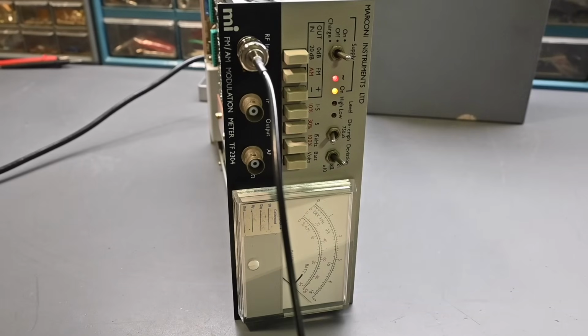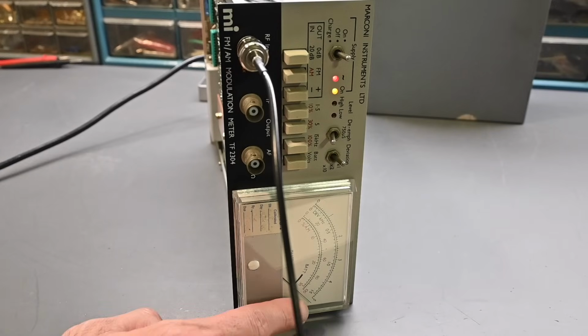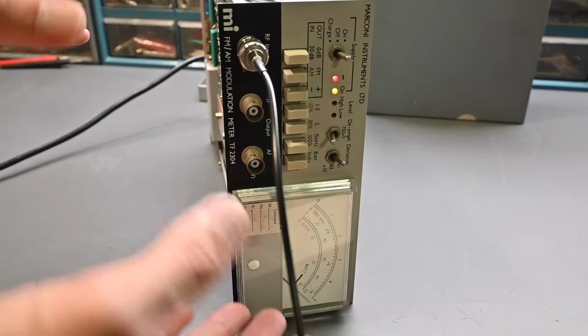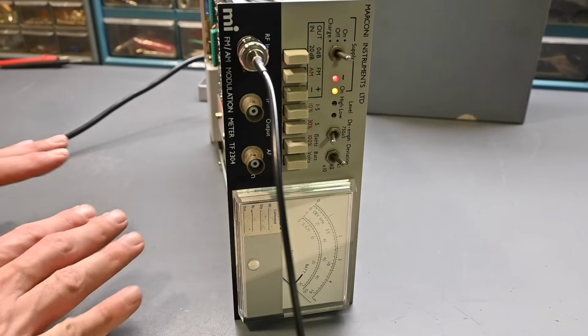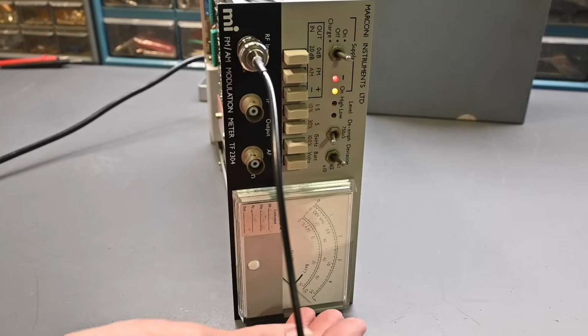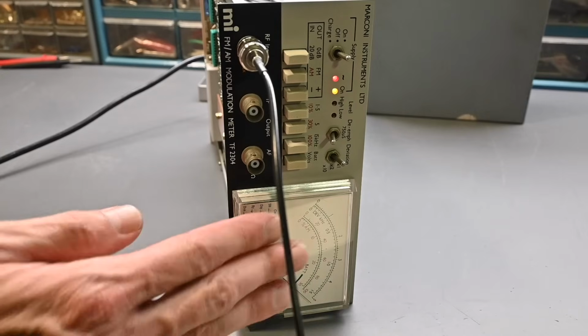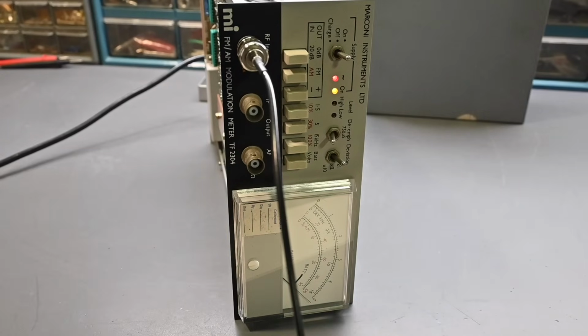So like before, it's at 300 megahertz, 5 kilohertz for the deviation, 1 kilohertz tone, and 0 dBm output. So full scale indication here. What I'll do is I'll make the adjustment and I'll turn the meter down flat and take a look at the setting, because with this turned sideways like this, that could affect the accuracy of the meter.